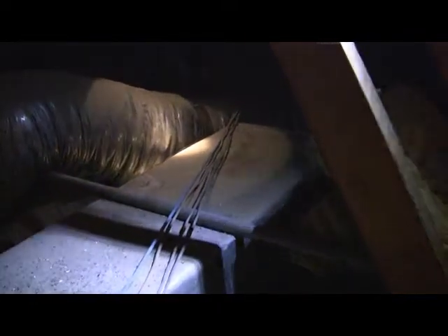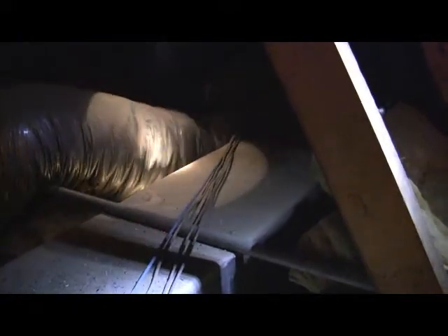So what we've got essentially, the way this was installed, was an open hole in the bottom of that return cavity that connects it to the floor joist or the rafter cavity that hasn't even been sealed on the back side of the ducting system to prevent it from pulling air from the attic directly. So we actually need to get to every one of these and seal the back side of the rafter cavity so that it's sealed off and not just pulling return air directly from the attic.